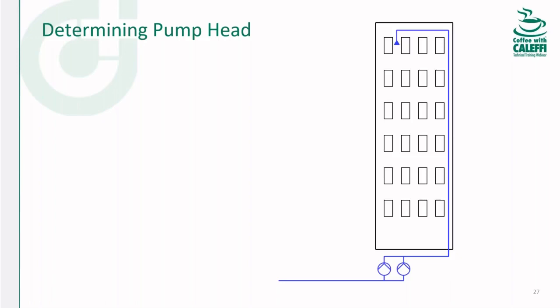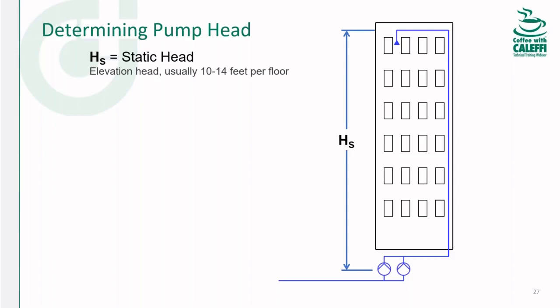All right, so back to the important stuff. Pressure is probably more straightforward, so let's start here. The first is static head, also called elevation head. That's the vertical distance that the liquid needs to travel all the way from the pump inlet to the highest point in the building. So in commercial buildings, like we said earlier, about 10 to 12 feet per floor, and that's going to add up real quickly. Next, we've got the friction head, and that's the loss through all the piping and the fittings from the pumps to the furthest fixture.